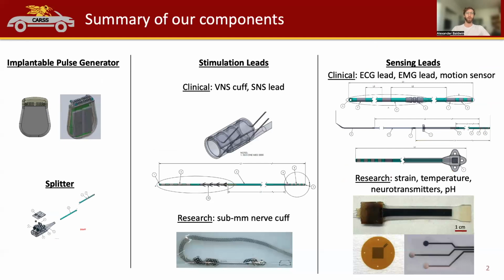So just to review, we're developing an IPG as well as several stimulation and sensing leads. Up to 8 of these leads can be used with the IPG, which we hope will provide the tools necessary to develop new, unique therapies. Right now, we have both clinical leads, which are based on existing leads, such as a bipolar VNS cuff or a linear sacral nerve array, and are being designed and manufactured by MedAlly under QMS, and then more research leads, which are being developed by the USC investigators to give new capabilities not yet seen in commercial devices. Our IPG uses standard ball seal connectors, so other leads can be designed and used with the OpenNerve system. And we have the capability to connect thin film devices with standard lead bodies for translational testing, if you're interested.